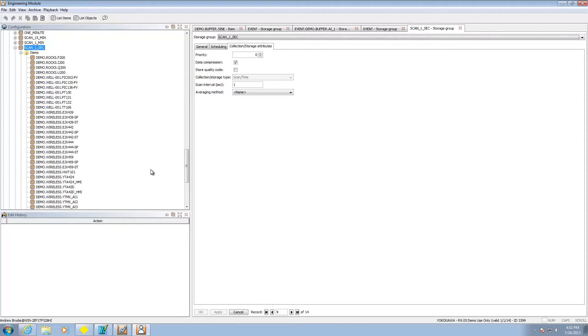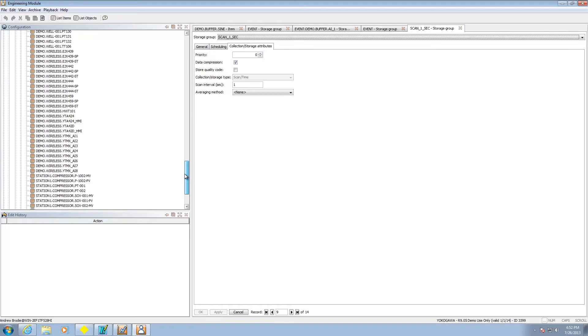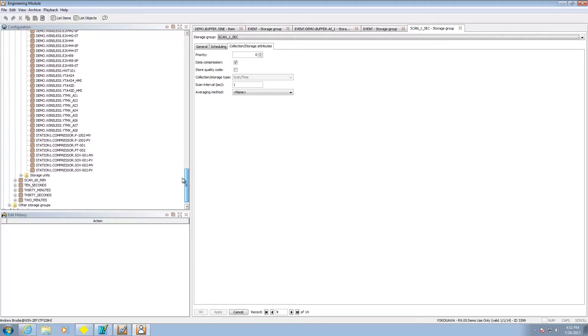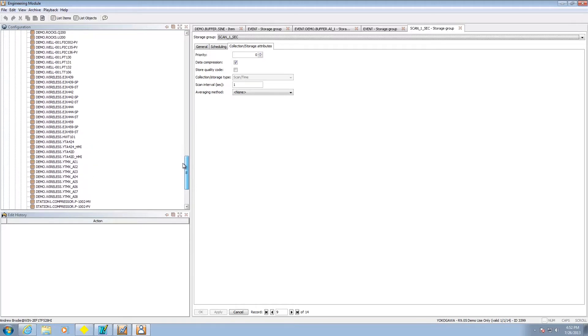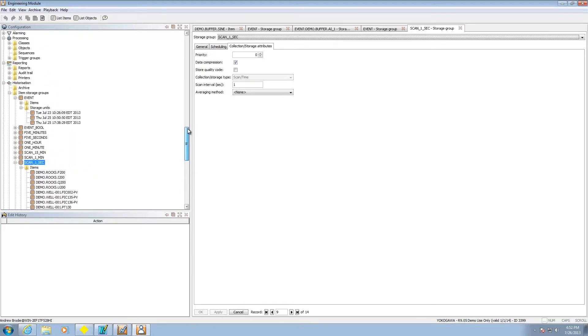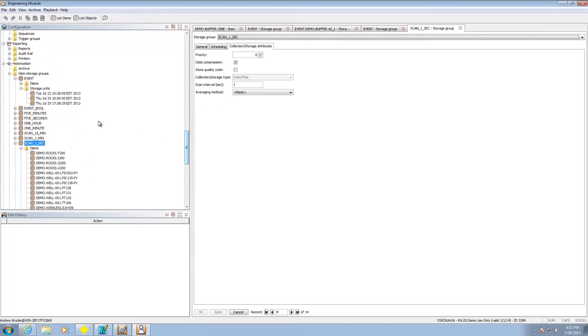This is really only going to be useful if the points underneath it are actually being measured once a second from the device. And remember where I showed you the fast scan time up top that was at a thousand milliseconds. So this would be a compatible scan rate for that particular item.